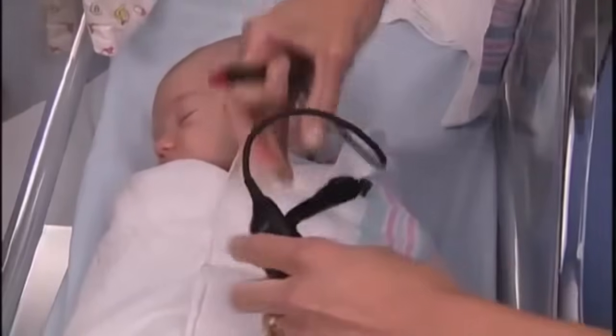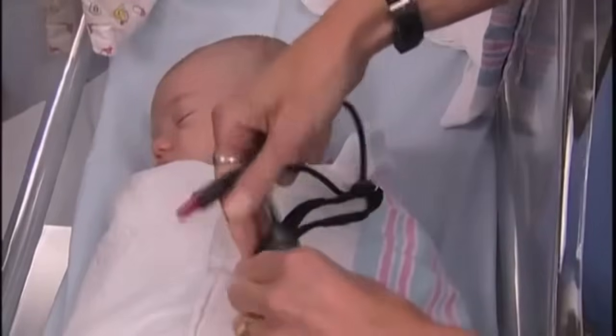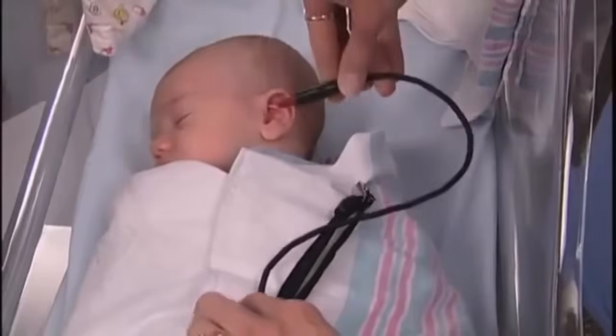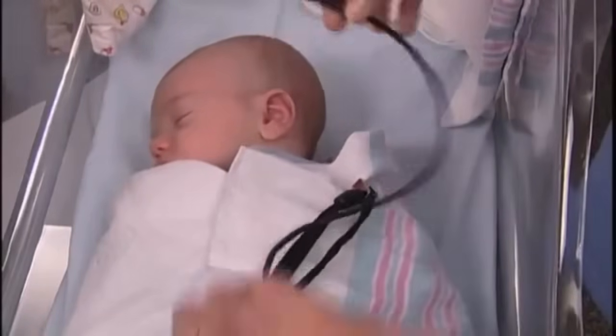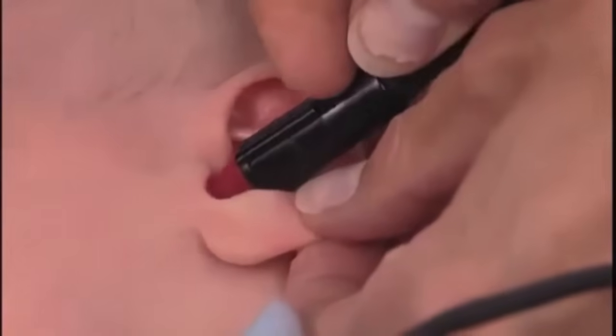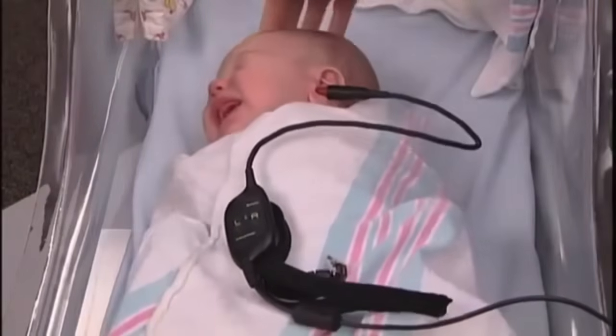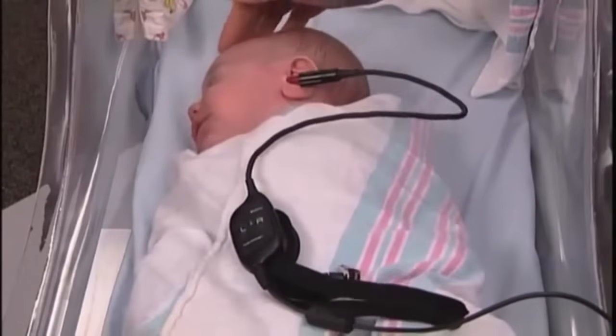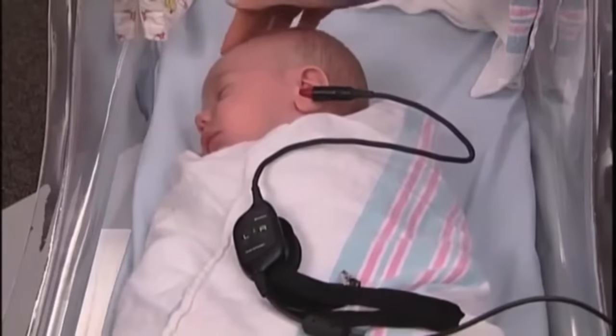To further assist you in reaching proficiency, please use these helpful suggestions. When testing newborns, as well as young children and people with multiple disabilities, using an external probe is extremely helpful in obtaining accurate readings. The probe allows excellent flexibility when positioning and using the instrument on these sometimes difficult-to-test subjects. When testing a newborn, you should position the probe enclosure so that there is no weight on the probe cable, and it is directed away from the newborn's hands. Once you have the probe enclosure placed correctly, push the probe into the infant's ear canal while gently pulling down and back on the pinna. This action straightens out the ear canal and reduces the chances of a read error due to the probe tip encountering the wall of the ear canal.